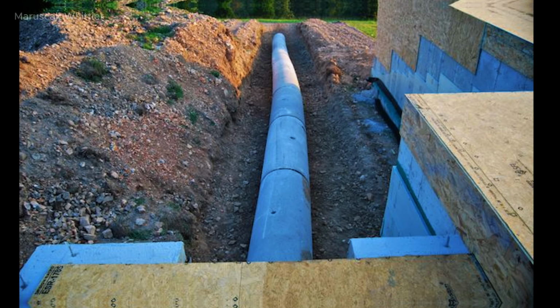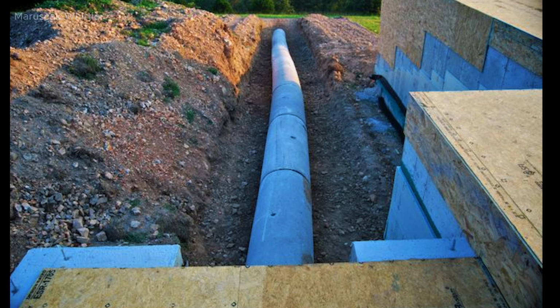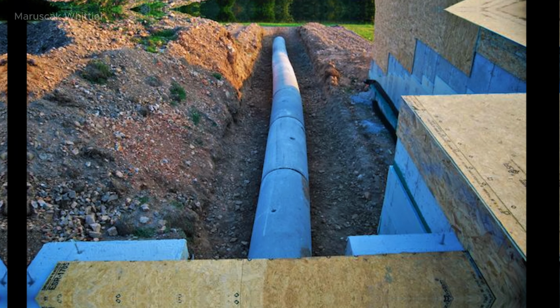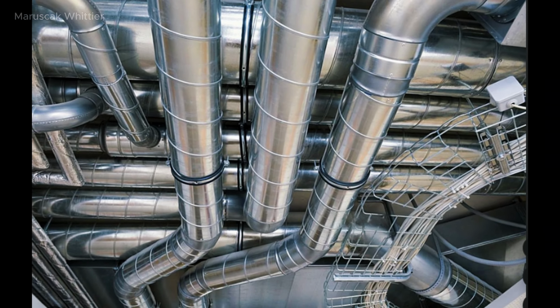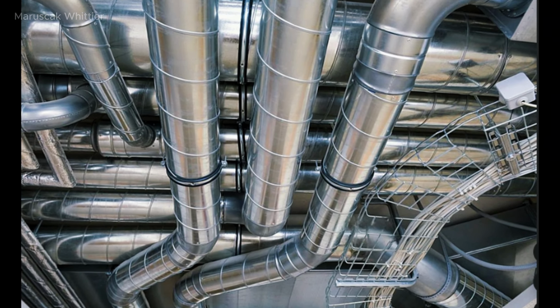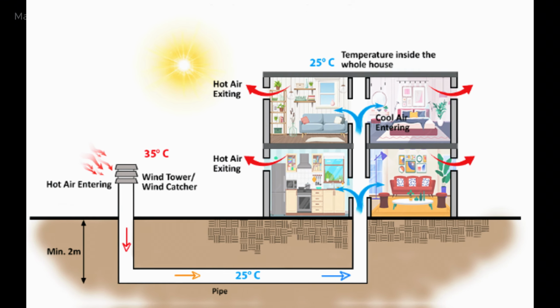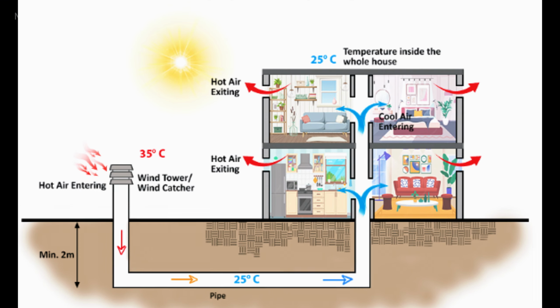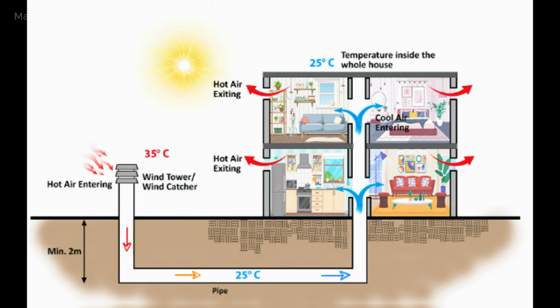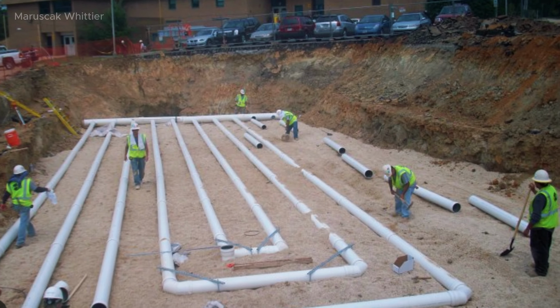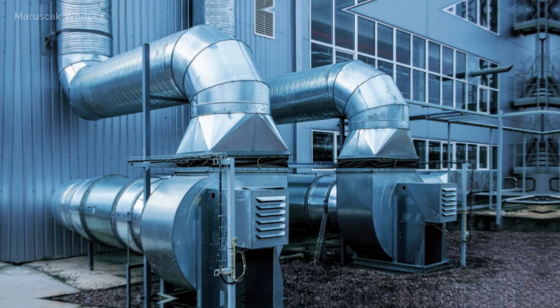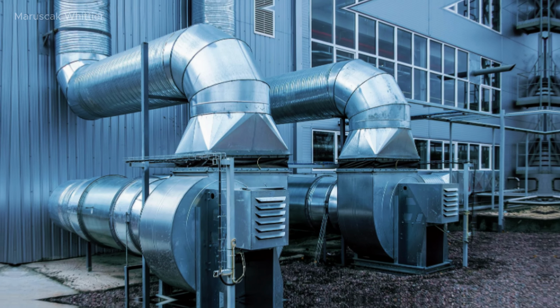This is why the smarter conversation separates open-air earth tubes from closed-loop ground loops. An open-air tube moves outdoor air through a buried pipe and into the home. A closed-loop system moves liquid through a sealed loop underground, then transfers temperature through a heat exchanger or fan coil. If the open-air earth tube is the folk version, the closed-loop ground loop is the version modern building science can trust more.